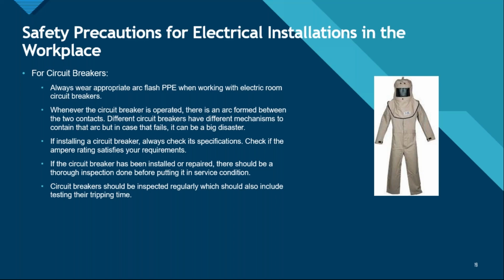For circuit breakers, always wear appropriate arc flash PPE when working with electrical room circuit breakers. Whenever you want to manually trip open a circuit breaker, always have your arc flash PPE. Always trip the circuit breaker with your right hand, and your body should be out of the way of the circuit breaker. Whenever the circuit breaker is operated, there is an arc formed between the two contacts. Different circuit breakers have different mechanisms, but if that mechanism fails, it can lead to a big disaster.